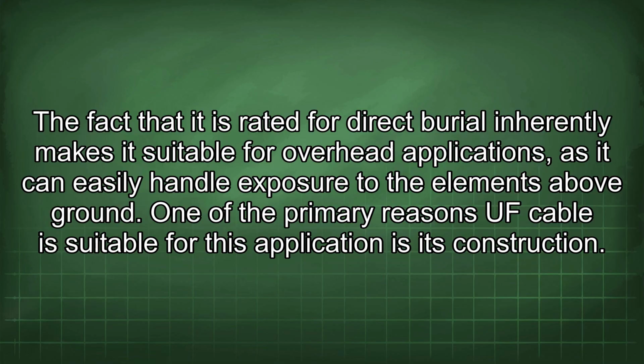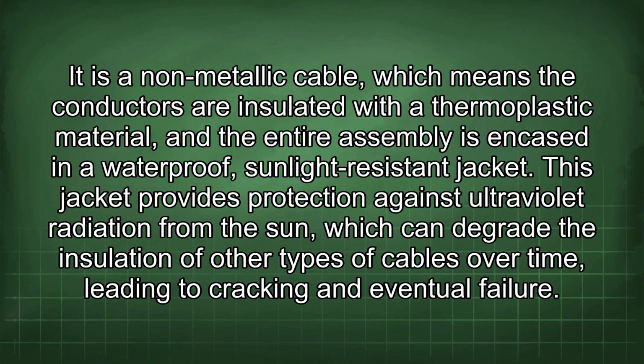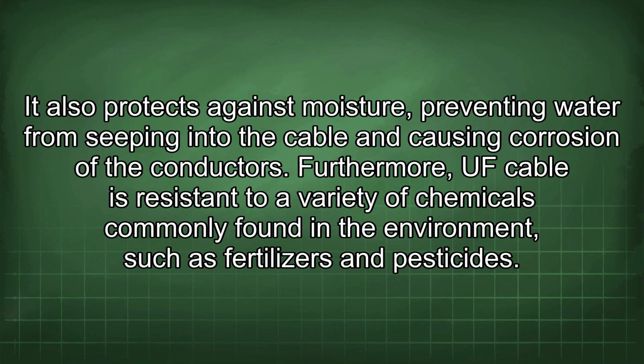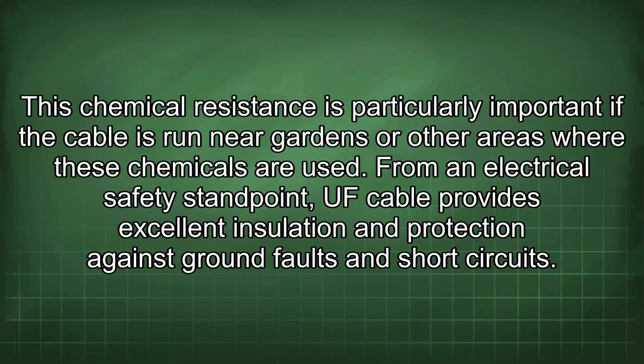One of the primary reasons UF cable is suitable for this application is its construction. It is a non-metallic cable, which means the conductors are insulated with a thermoplastic material, and the entire assembly is encased in a waterproof, sunlight-resistant jacket. This jacket provides protection against ultraviolet radiation from the sun, which can degrade the insulation of other types of cables over time, leading to cracking and eventual failure. It also protects against moisture, preventing water from seeping into the cable and causing corrosion of the conductors. Furthermore, UF cable is resistant to a variety of chemicals commonly found in the environment, such as fertilizers and pesticides. This chemical resistance is particularly important if the cable is run near gardens or other areas where these chemicals are used.